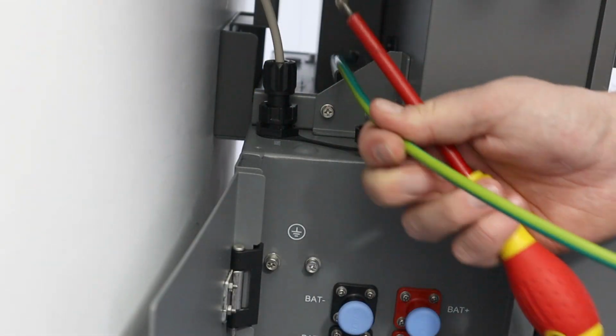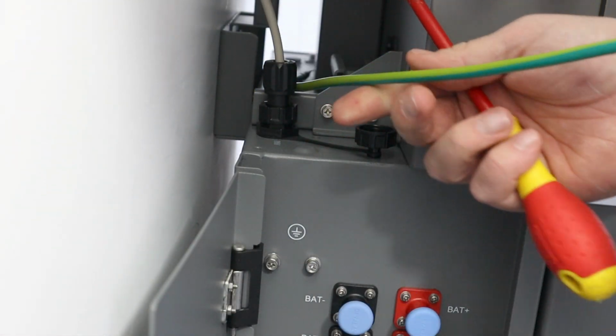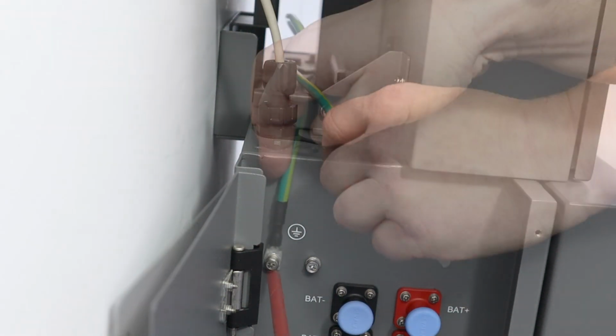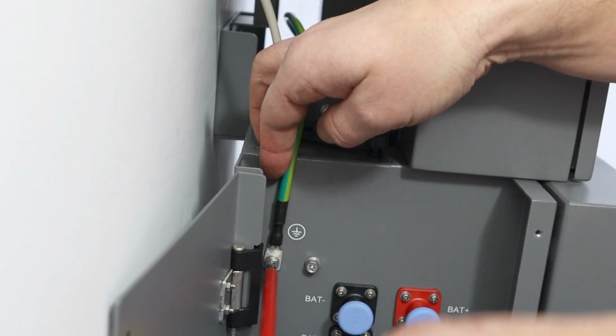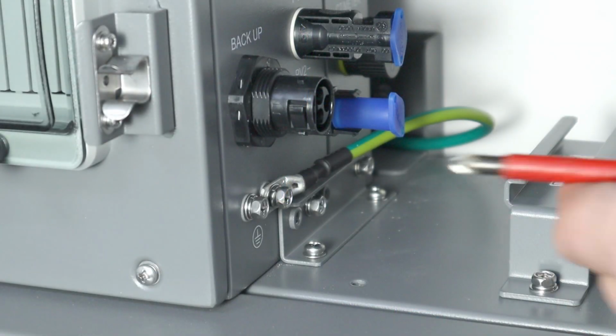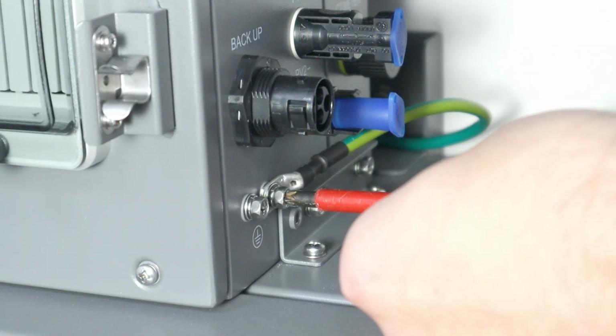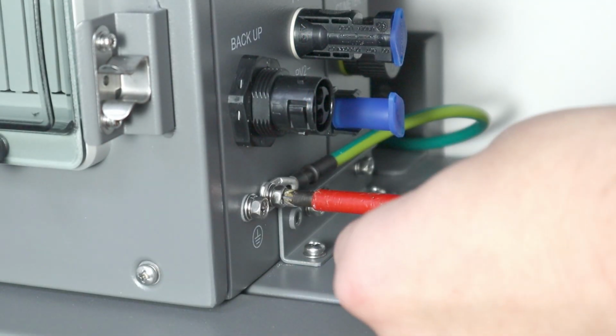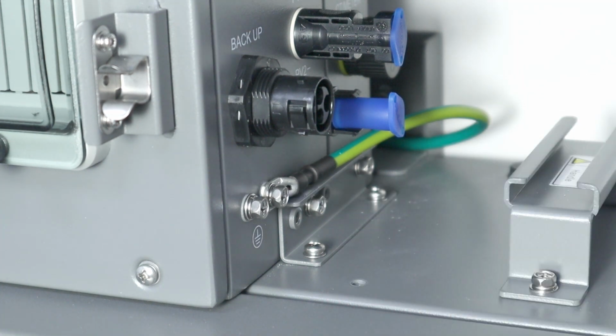Slide the supplied battery inverter earth cable through the gap to the rear of the inverter and connect to the earthing point on the battery. Next, connect the other end of the earth cable to the earthing point on the opposite side of the inverter.